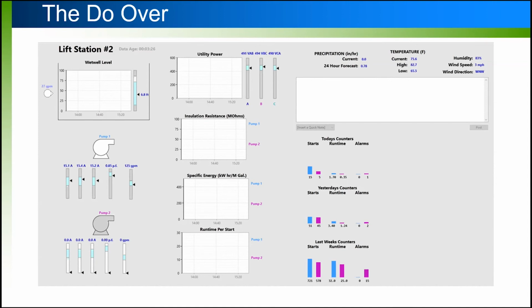Specific energy, like I mentioned, could also be shown. I would show it on a graph now. I would keep weather in, but I put weather off to the side, because weather isn't really going to help you troubleshoot any issues you're having currently at a lift station, but it's nice to know. And then I added in counters, and I used bar graphs so you can easily compare your pumps, because at a lift station you generally have the same number of starts. You're alternating, right? So your starts should be relatively the same, and then you hope your runtime is also relatively the same, because if they're off, then probably one of those pumps is clogged. So I put those together so you can easily compare pump to pump. So this is the initial improvement to that screen.